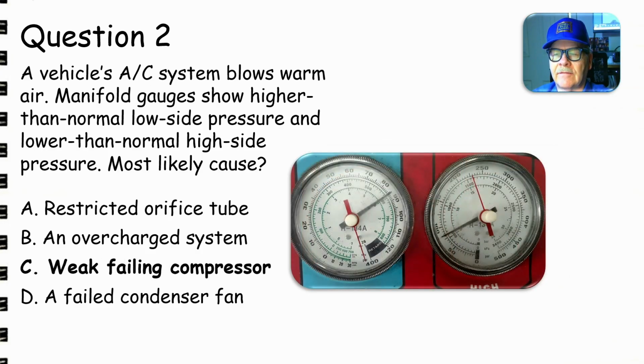This is a weak and failing compressor. This is one where I took a video of the gauges in the shop. This was a scroll compressor. Scroll compressors love to fail. They don't take a lot of energy to turn, not like a regular piston compressor. The way they're designed, they work really well when they're working, but they like to fail. The seals on the end of the scrolls mess up, and it's just real easy.